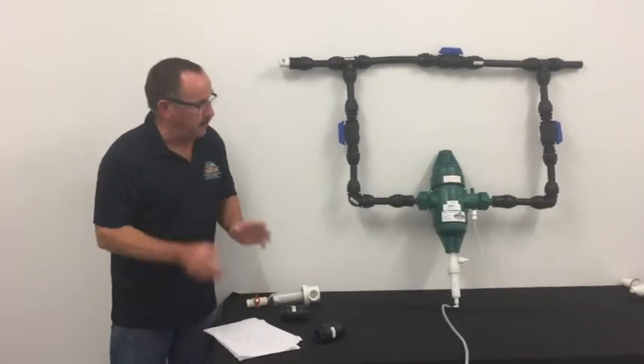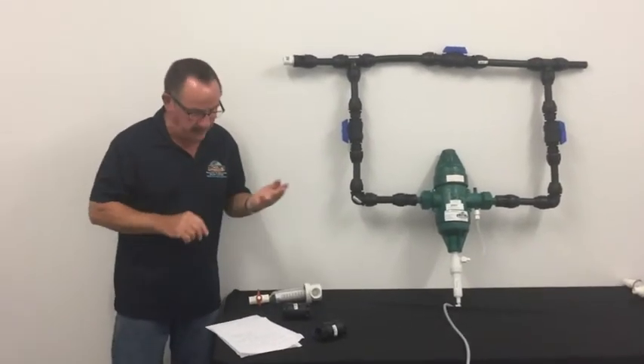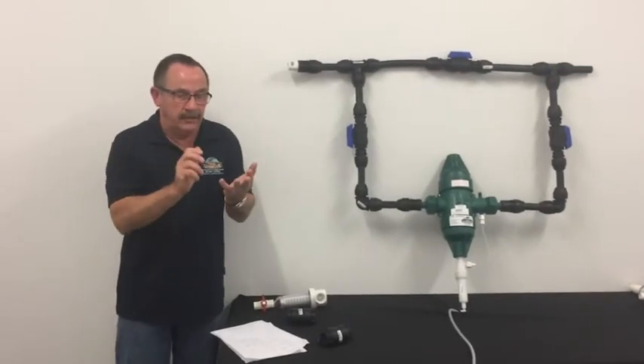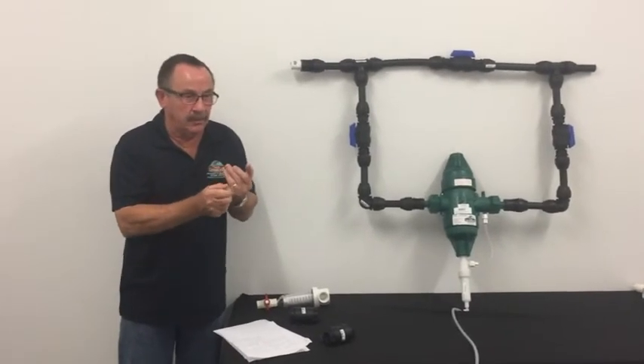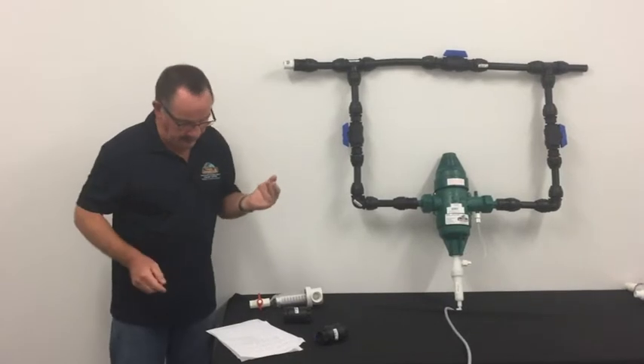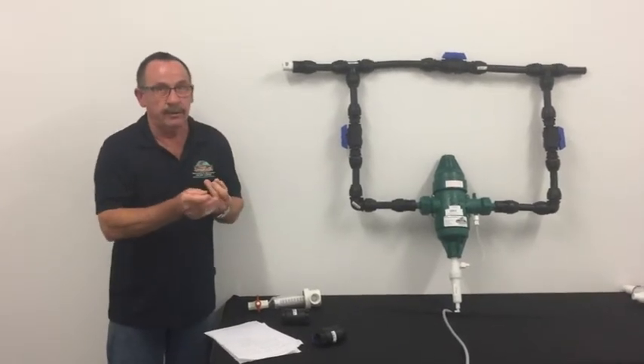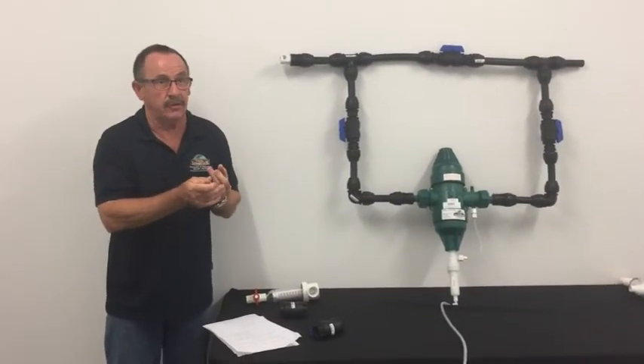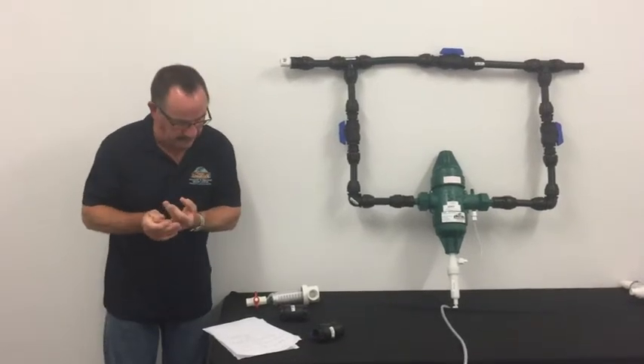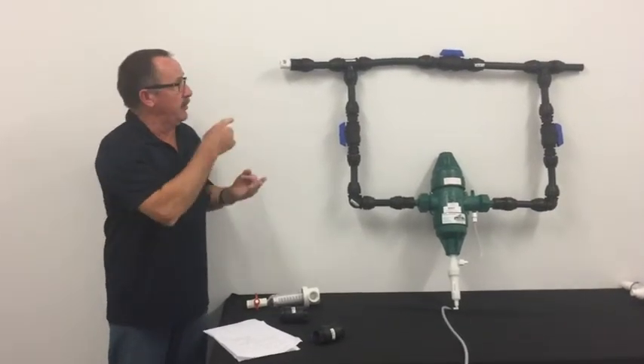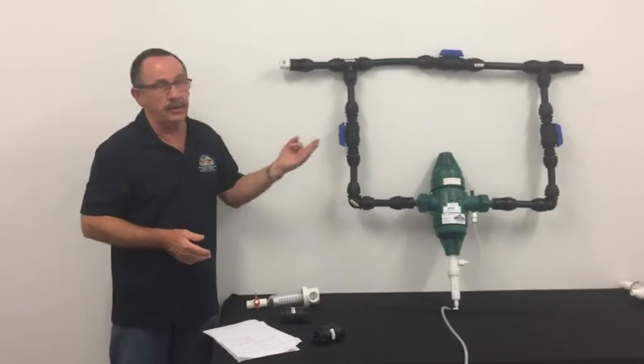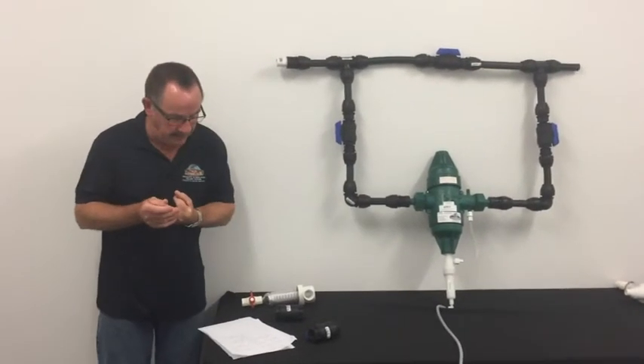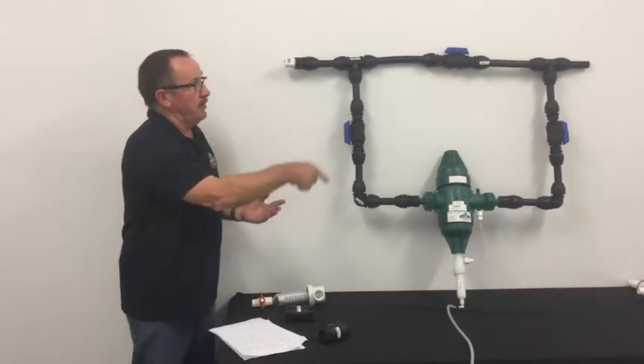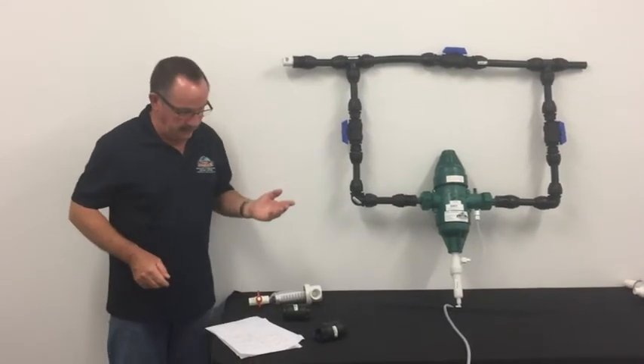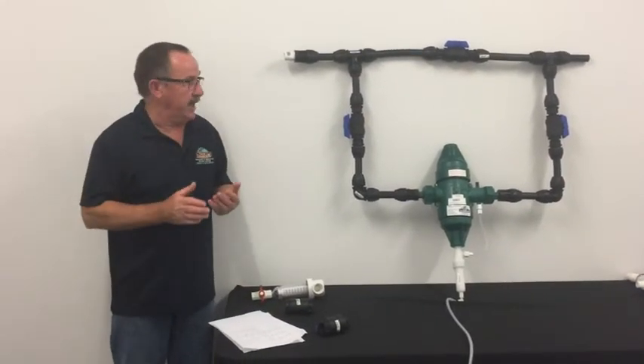Just summarising the 5 key things to make sure you get right: set up something that's not a permanent setup so that you can remove the doser if you need to. Use a filter if you can, one that's suitable to your particular situation. Use an appropriate size pipe - 1 inch is usually good enough, but bigger if you need to. Have a bypass like this so that you can remove the doser when it needs servicing.